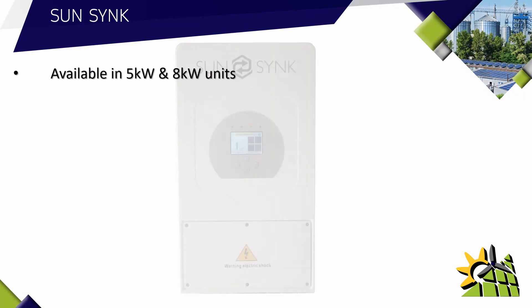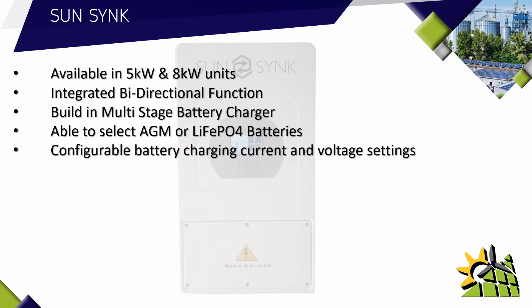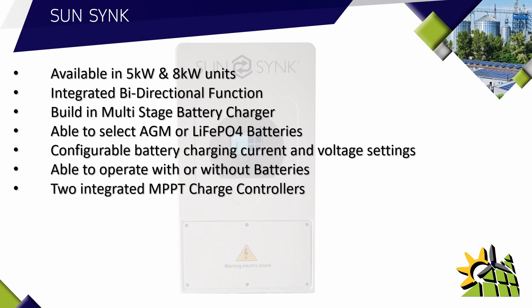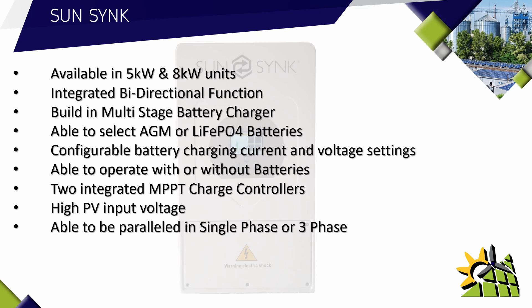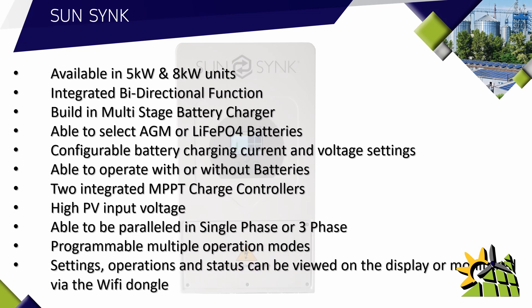Let's take a closer look at the Sun Synk inverter. These units are available in 5kW and 8kW. It has an integrated bi-directional function and a built-in multi-stage battery charger able to charge AGM or lithium phosphate batteries. The battery charger can be configured to the correct charging current and charging voltage. This inverter is able to operate with or without batteries. It has two integrated MPPT charge controllers with a high input voltage. The inverters can be paralleled in single phase or three phase, and are programmable with multiple operation modes. Settings, operation, and status can be viewed on the display or monitored via the integrated Wi-Fi dongle.